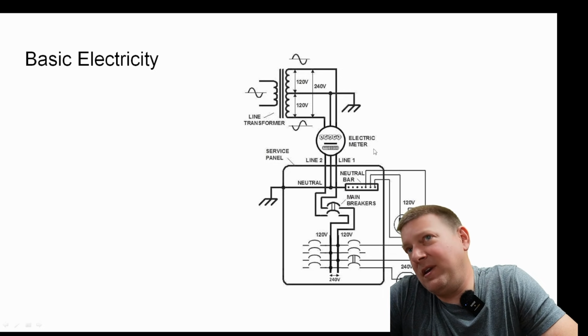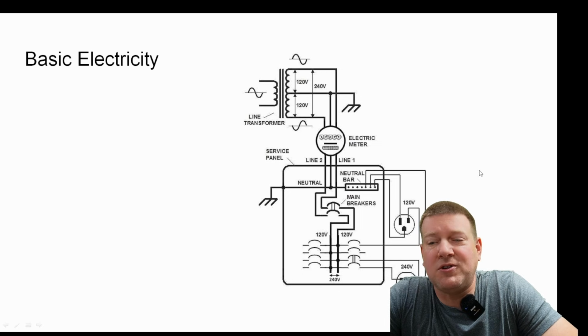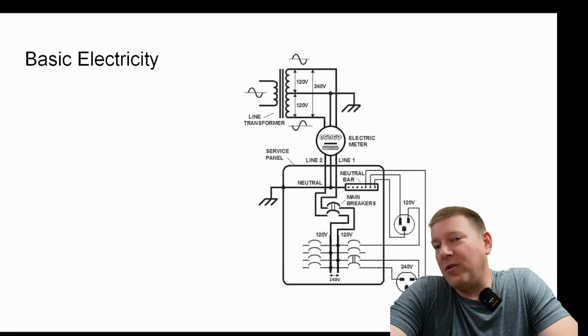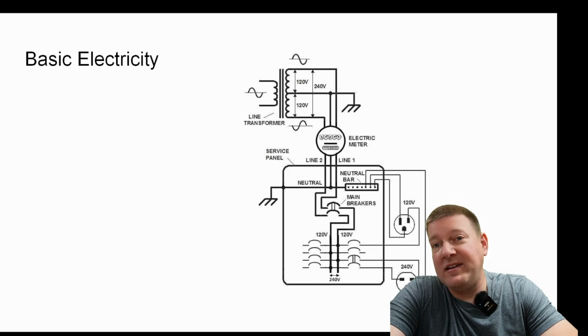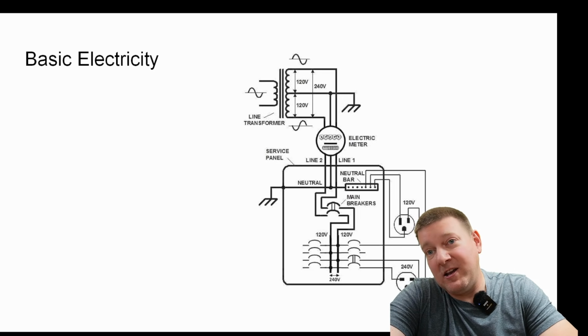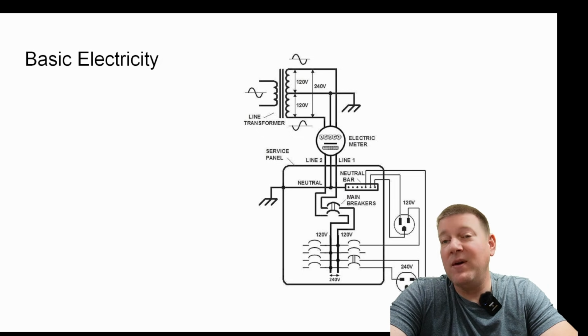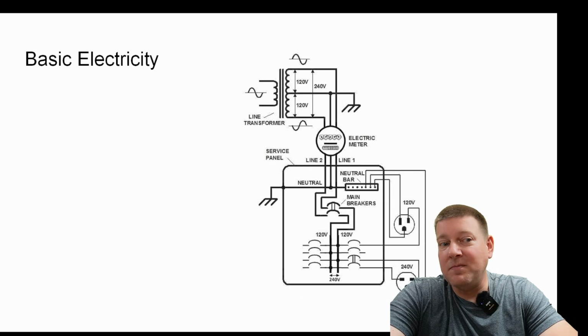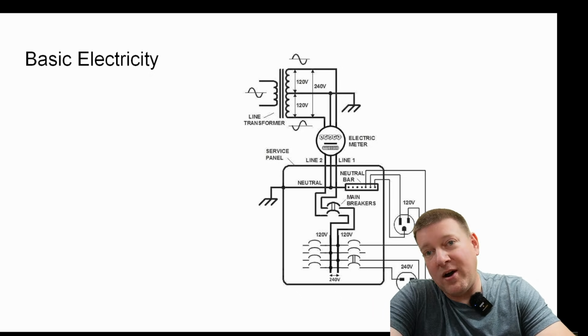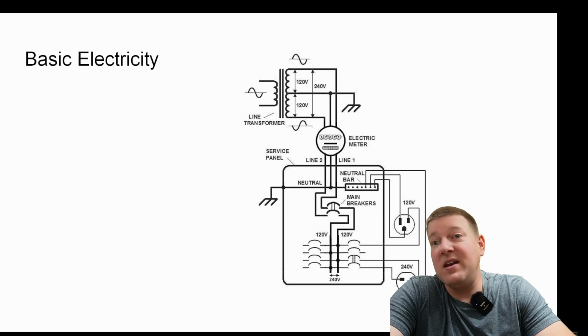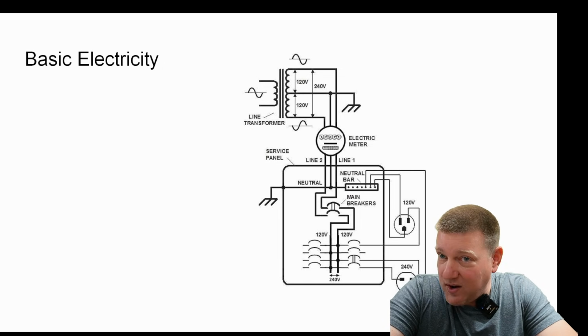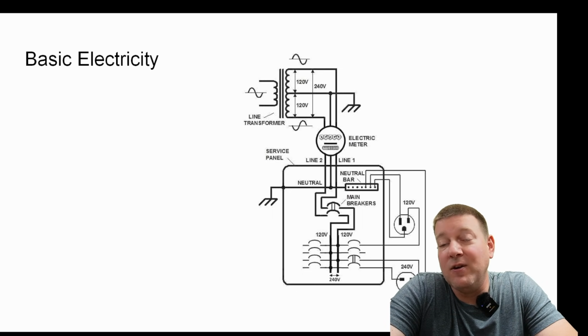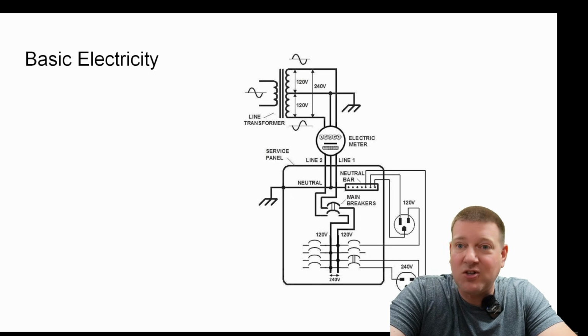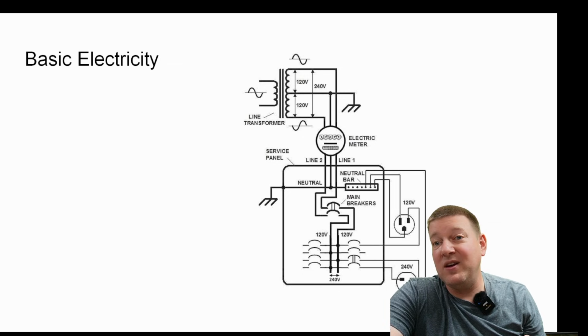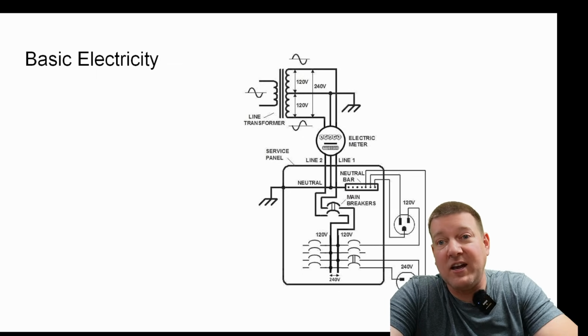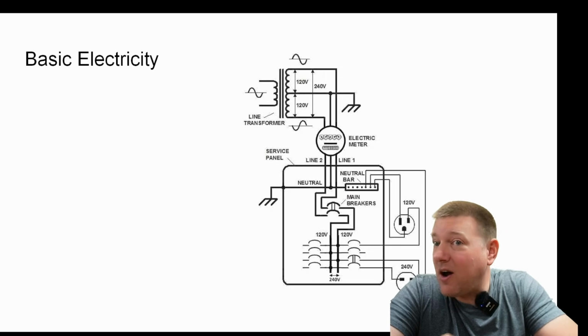Okay, so this is a rough diagram of a house electrical system, and just to let you know, all the grounds go all the way back to the control panel, and they're all bonded together. And the neutral is also bonded to the ground, and they're at the same potential. Now, as I said earlier, and I'm going to highlight this, if you have an open neutral or an open ground, those conductors will be antennas, and they will start creating voltage and be an antenna for noise. So that's why, through our electrical safeties, we verify the integrity of ground, not just for leakage currents, but because those extra conductors can and will conduct noise from everything, especially like the lights. And they will start creating an electrical current, which becomes a leakage current, right?